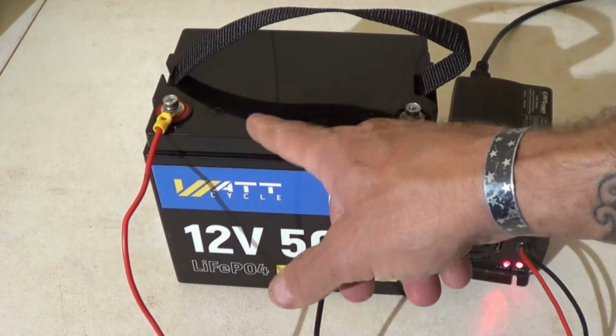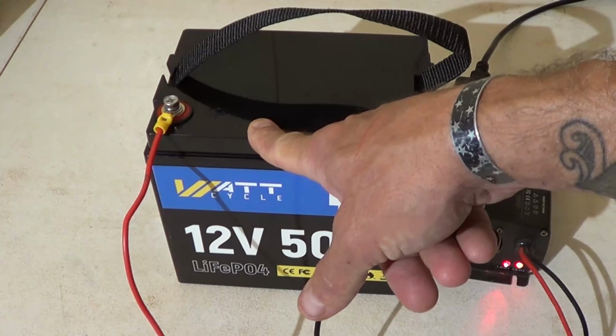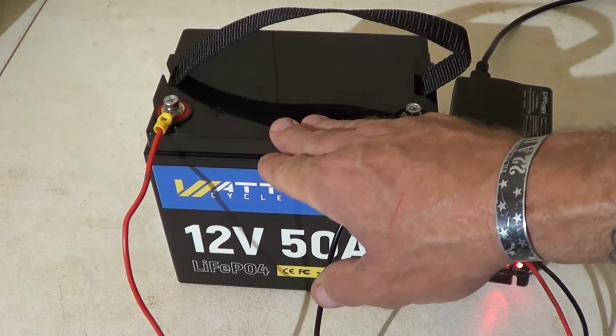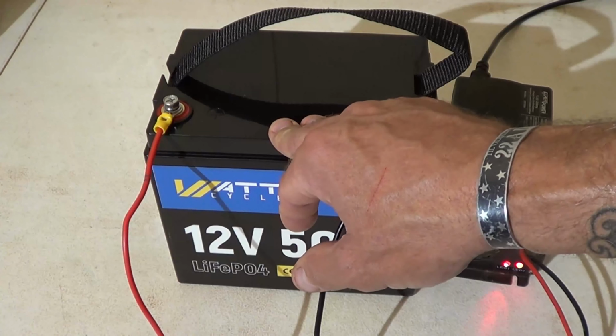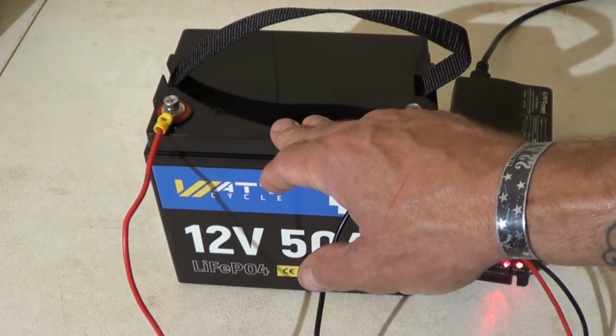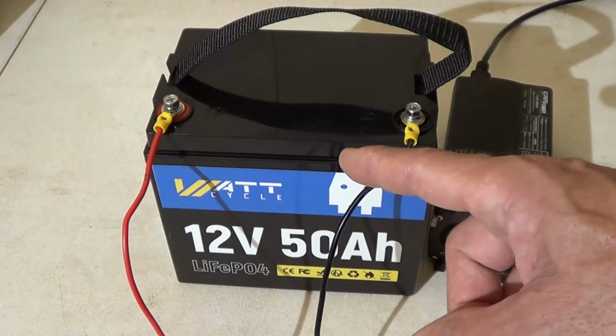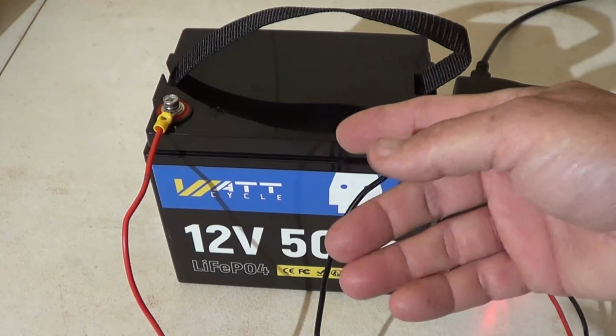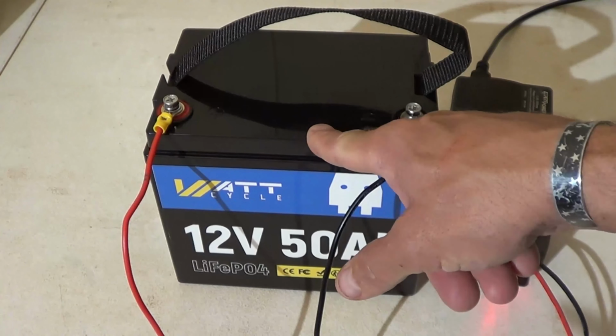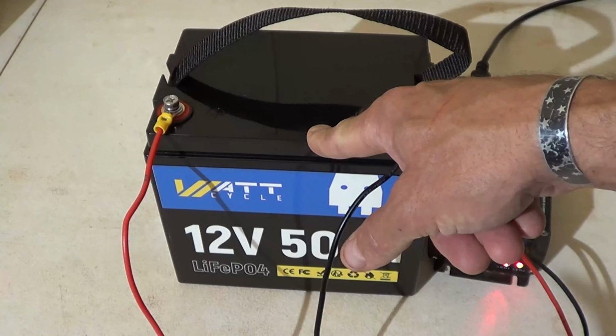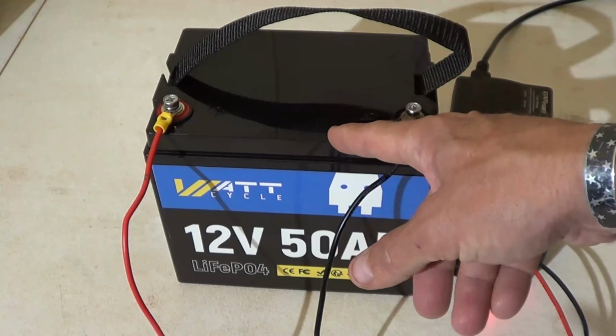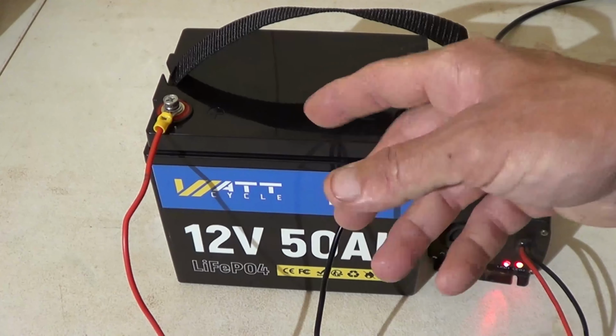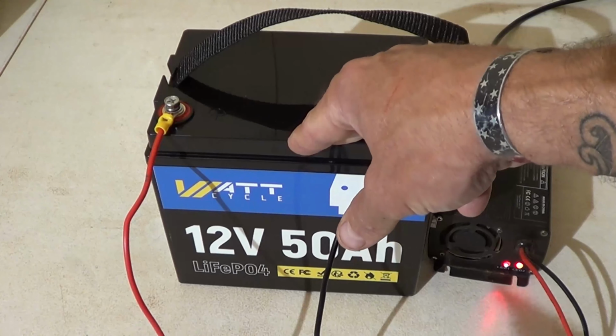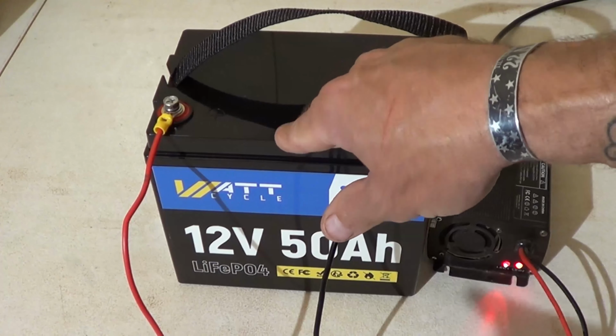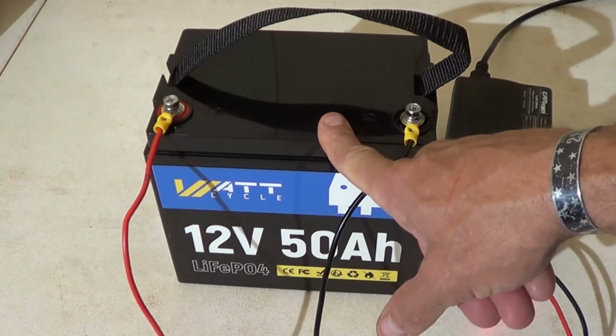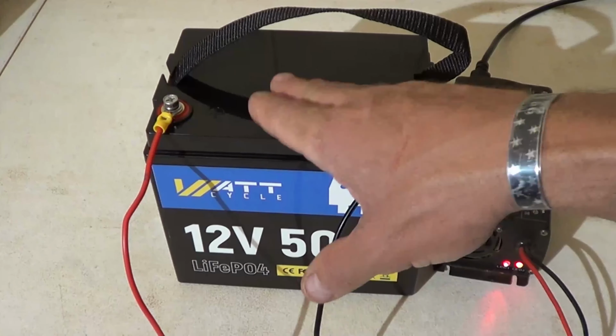That is fantastic. You also have the overcurrent and short circuit discharge protection. If the overcurrent or short circuit protection is tripped, the BMS will shut down the battery and it will remain disconnected until you remove the battery cables. When the battery cables are disconnected, they suggest that you check the battery voltage with a voltmeter, and if it reads above 10.8 volts, go ahead and reconnect the battery cables. If you're unsuccessful in obtaining a voltage above 10.8 volts, they say that you need to contact the WattCycle Technical Customer Support Team.